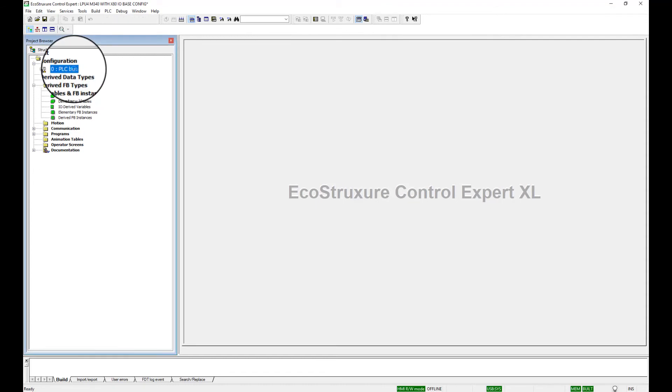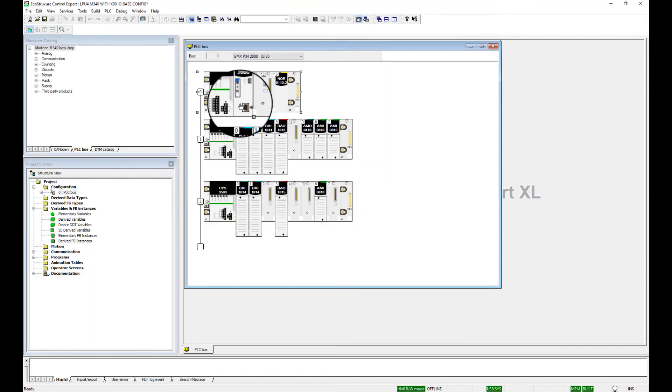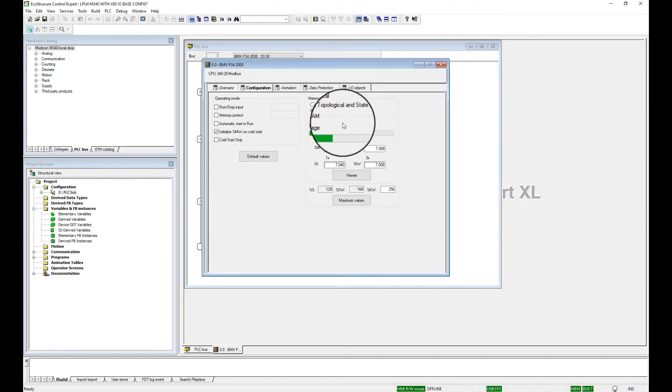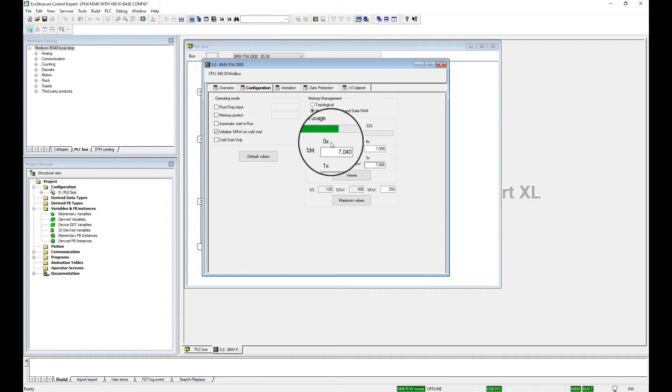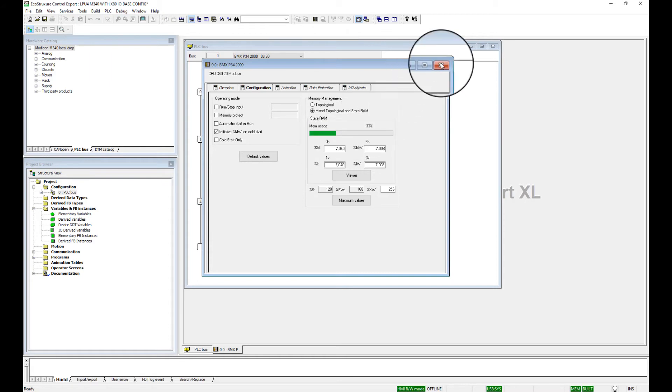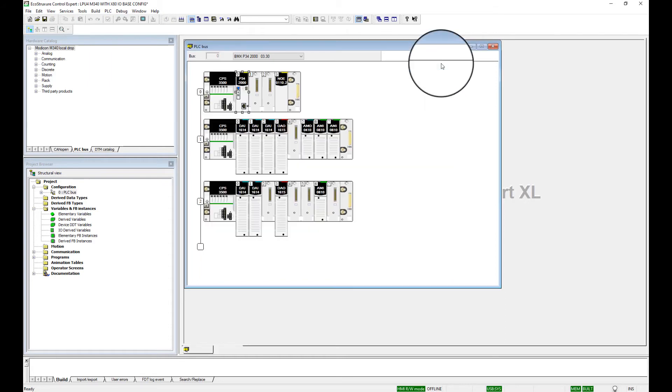Using the spreadsheet created earlier, open the PLC bus screen. Double-click the P34-2000 processor screen, and in the Configuration tab, set the memory management to Mix, Topological, and State RAM. Set the %M, %MW, %I, and %IW values equal to those values recorded from the original Quantum program. Close the BMX P34-2000 screen.